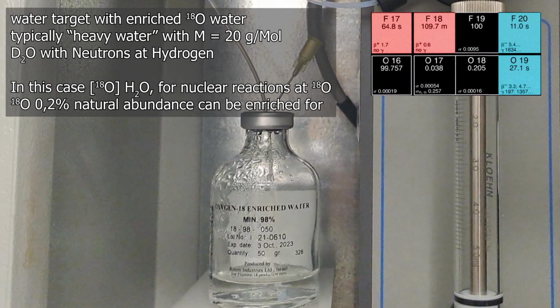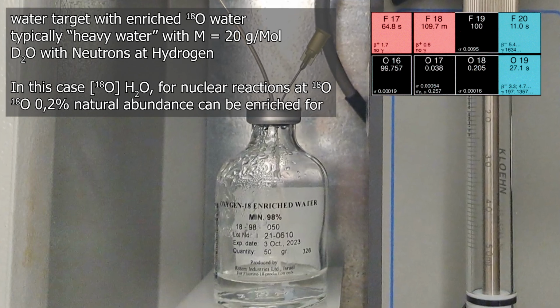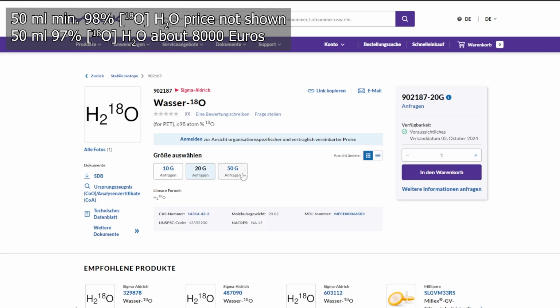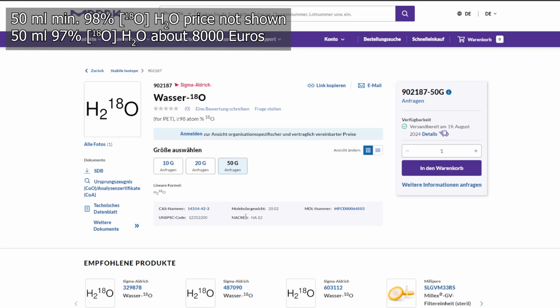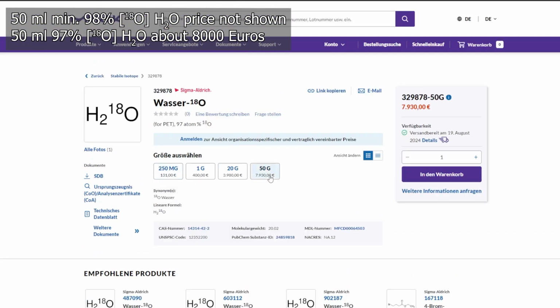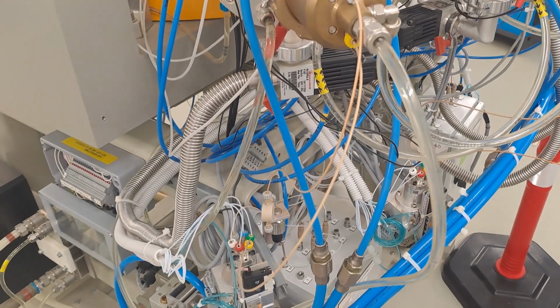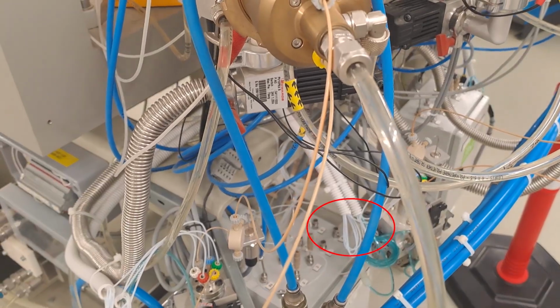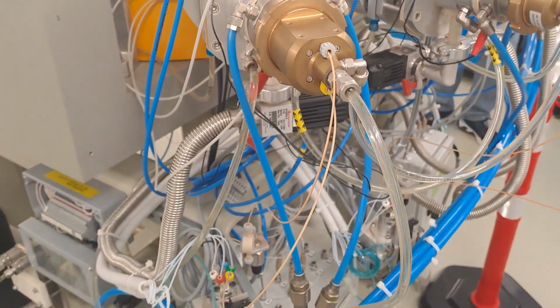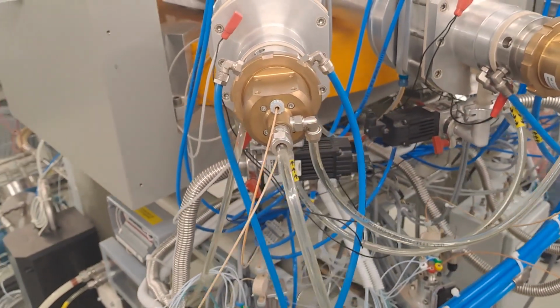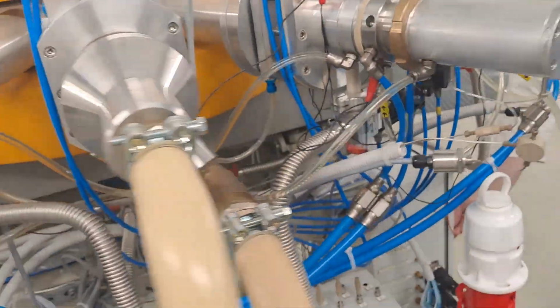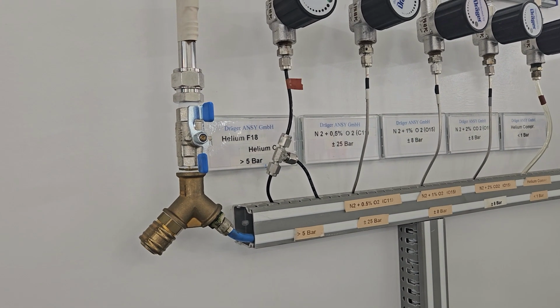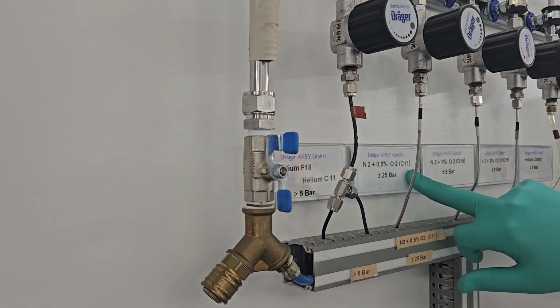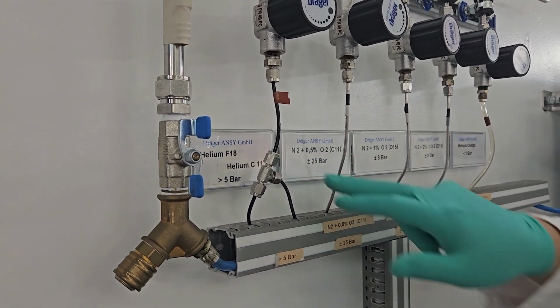At least 50 milliliters of oxygen 18 water enriched to 98% is needed. Just to give you an idea of how expensive that is, look here. This is then pushed through the capillary. The 3 milliliter column isn't further subdivided. At this stage, the water is not active yet. By the way, it's transported using gas. In the capillaries, there's helium in front of and after the water column.